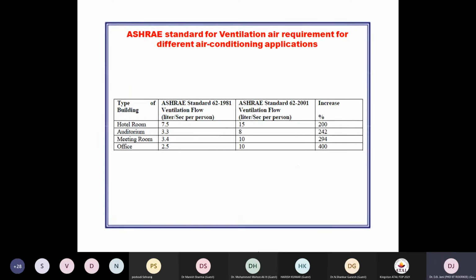Our conventionally used split AC does not provide any ventilation airflow. The one pipe connecting the indoor to the outdoor unit carries only the refrigerant flowing in and out. If you do not open the door and window and sit inside a room that is closed 100%, typically for more than 10 hours, it causes a serious effect on the health of people because of the lack of oxygen. So ventilation airflow should be there whenever a particular HVAC system is formulated as per the requirement and design standard of ASHRAE.